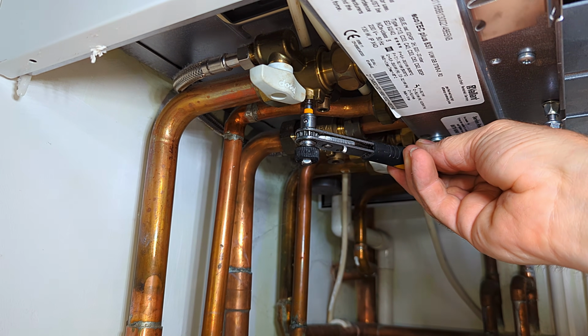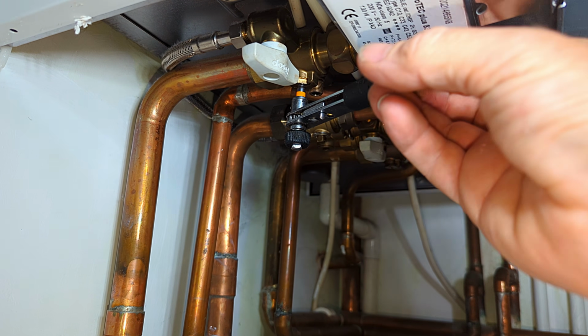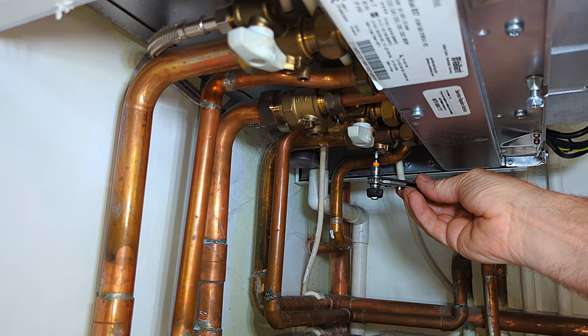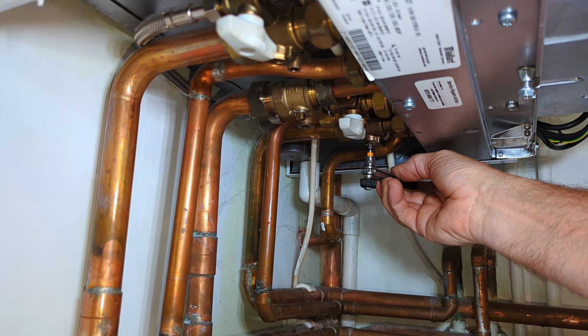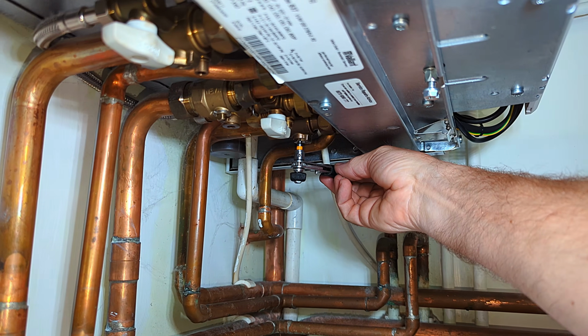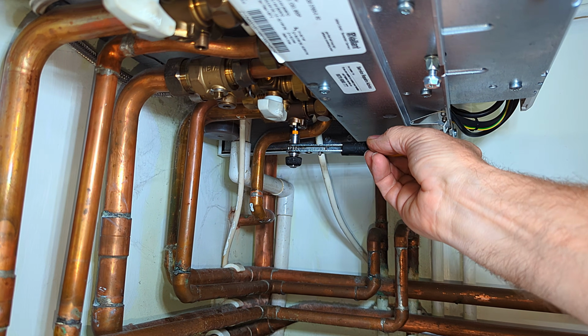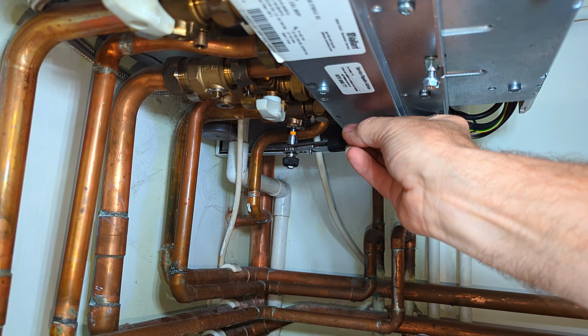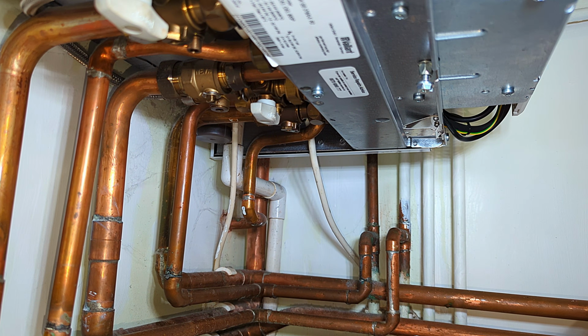I can now open up the flow and return valves. So that's the flow valve open, and then I'm going to open the return valve. As I open the valves, I may hear some water rush into the boiler, as the pressure inside the central heating system is still higher than the pressure within the boiler.